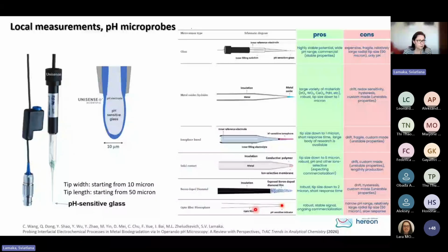We have been using Pyroscience microoptodes for over 10, 12 years. We started at the Técnico in Lisboa and still continue using them. So they possess a very stable signal, very low detection limit, high selectivity, and they are quite affordable. These microprobes are temperature sensitive, which is neither advantage nor disadvantage. It's just a property that you need to take into account. Basically, any measurement with an optode needs to be compensated for temperature, and this is quite easy if you use equipment from this company because it's all provided in the same package. Well, the only disadvantage here is a somewhat larger tip, again, 50 to 70 micrometers.